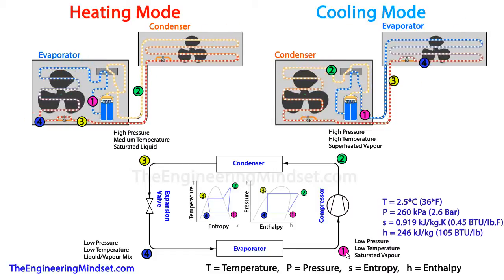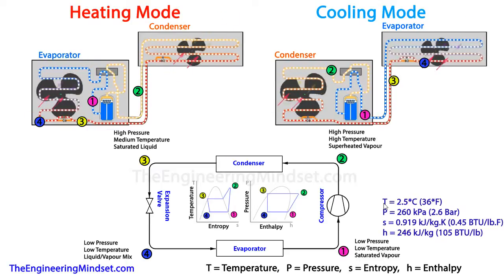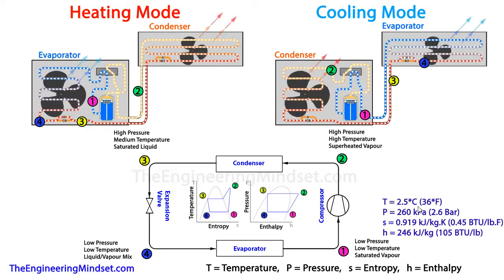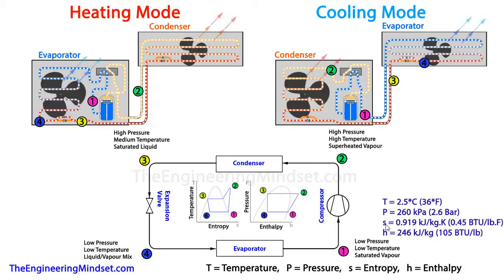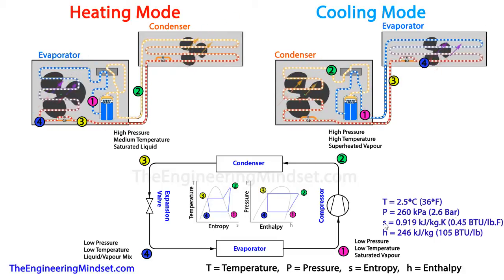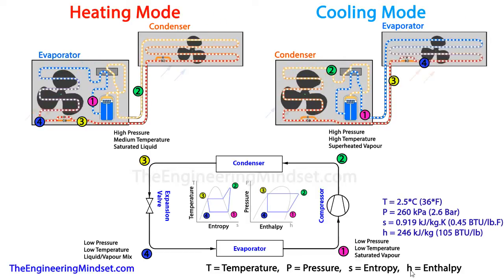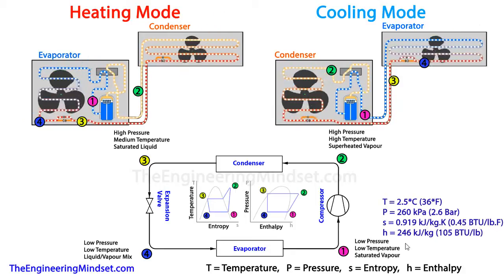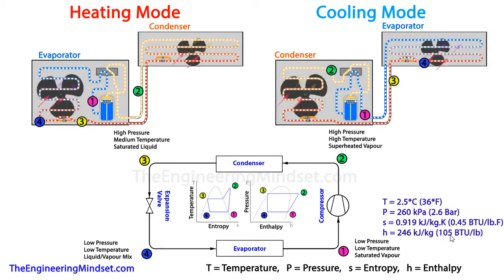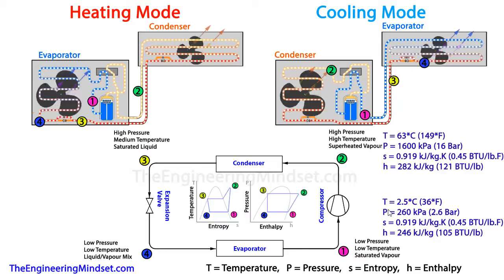Now for the numbers. At Point 1 — the low-pressure, low-temperature saturated vapor — we start with a temperature of about 2.5°C (36°F) and a pressure of 260 kPa (2.6 bar). The entropy is 0.9 kJ/kg·K (0.45 BTU/lb·°F) and the enthalpy is 246 kJ/kg (105 BTU/lb).